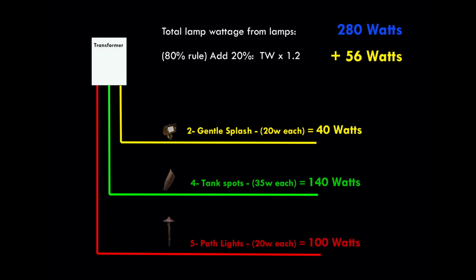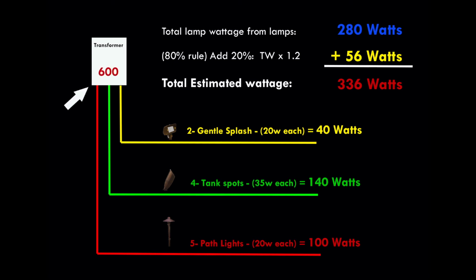This will show that there is potentially a consumption of 56 watts just in wire resistance. When we add up our total wattage plus 20% potential resistance consumption, it leaves us with a total load of 336 watts. Well, this is well over the 300-watt rated capacity of the transformer. To use a 300-watt unit on this system would simply be asking for trouble. For this system, you're going to want to choose a 600-watt transformer at your time of purchase.